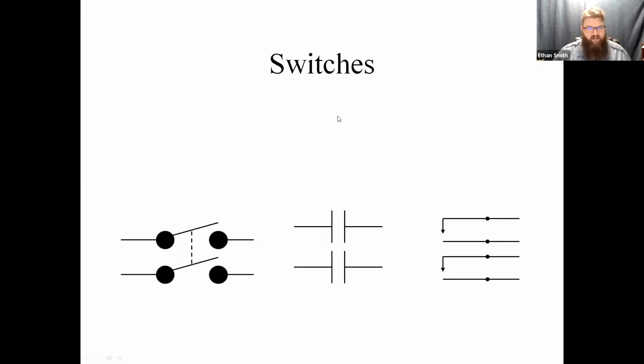Okay, it is a single pole, but actually it's not a single pole. Sorry about that. That is a double pole, single throw. So it has two armatures, but only one closed position. It can either be open or closed, but it doesn't have any extra sets of positions. So double pole, single throw, with the two contacts. This is another way you'll see this. You see this on peanut relays, things like that, quite a bit.